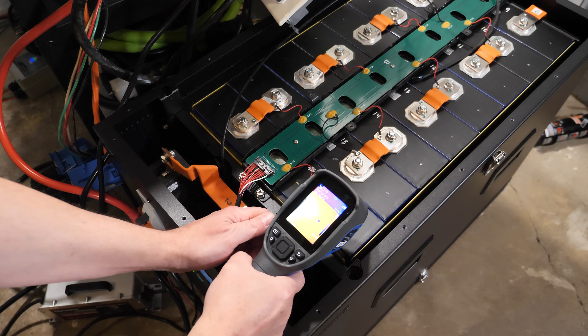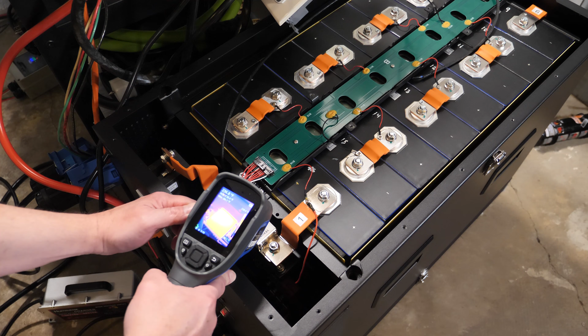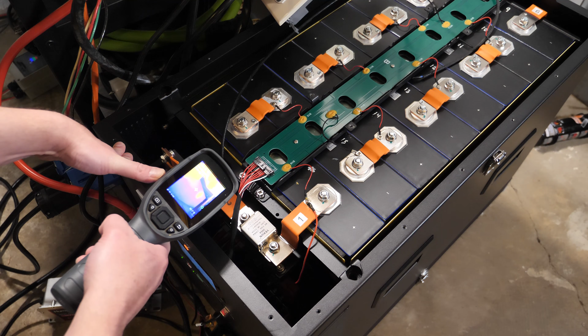Next thing we'll do real quick is we will take a look at some temperature readings. If you want to see real quick the amp draw on here, we're sitting at 249.3, which is pretty much on par with the JK BMS. Okay, I'm just gonna read these off to you so I don't have to keep it all in focus all the time. Cell 16 right on the top is 105 degrees Fahrenheit. We move to the bus bar right here, we're at 148, 150 degrees Fahrenheit. Just a little bit lower on the bend, we're doing 166. Move over to the fuse, we're still running at 235, 236. Move over to the bus bar over here, we're doing 195.7 degrees Fahrenheit.